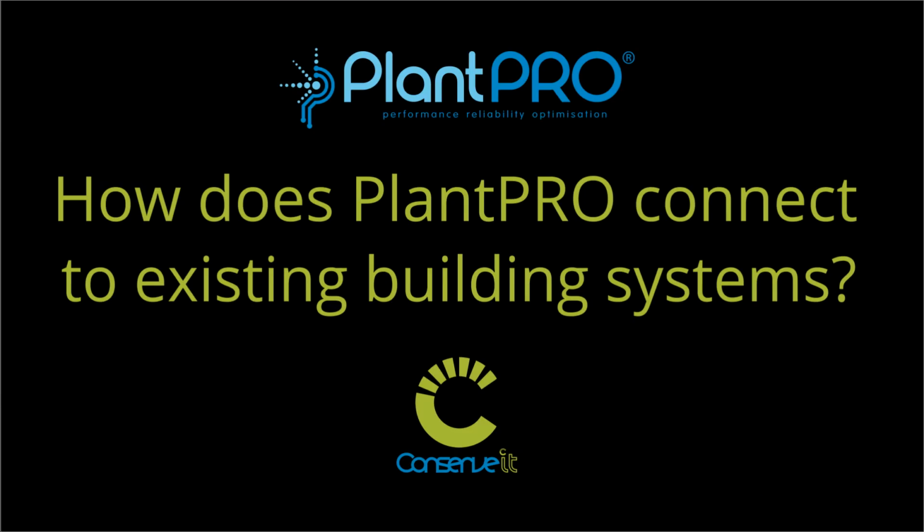The better the data, the better the decisions that PlantPRO can make. How does PlantPRO connect to existing building systems? PlantPRO is built upon the Niagara framework, so there's a lot of flexibility in how it can be integrated into the chiller plant. If there's already a BMS system, PlantPRO can communicate to the BMS system via BACnet, via LON, via Modbus to bring in the sensor data, make decisions and then send down the control outputs.